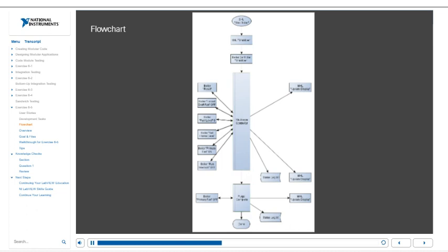During the Shutdown Controller phase, the boiler controller sends a reset message to the boiler. Once the boiler responds that it has reset, the boiler controller sends a message to update the user interface. Next, the boiler controller sends messages to the boiler to turn off the forced draft fan, set the fuel level to 0, and set the flame level to 0.